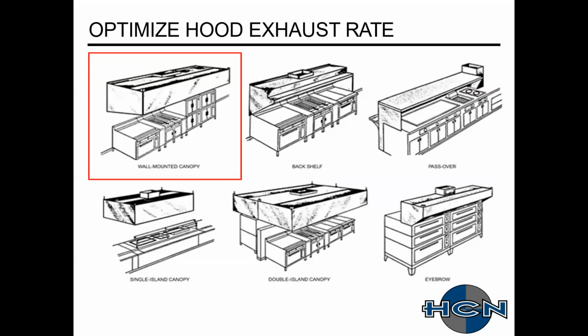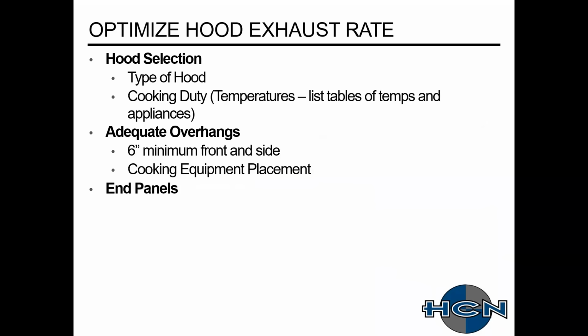So like a back shelf hood's not going to be very good at covering a double stack convection oven. Those are typically meant for countertop kind of equipment. Those ovens are going to overhang that back shelf, because typically a back shelf hood is narrower and a lot closer to the cooking equipment. A lot of places you'll see back shelf hoods are your fast food and quick service types of restaurants, Five Guys, McDonald's, Burger King, that kind of stuff. You see these a lot. Or you'll see the pass-over hood as well. Don't see it as much with Passovers. Typically, for most institutional cooking and quick service restaurants, you'll see a wall mount, a back shelf, or an island configuration. So like I said, with hood selection, your big thing there is what type of hood.